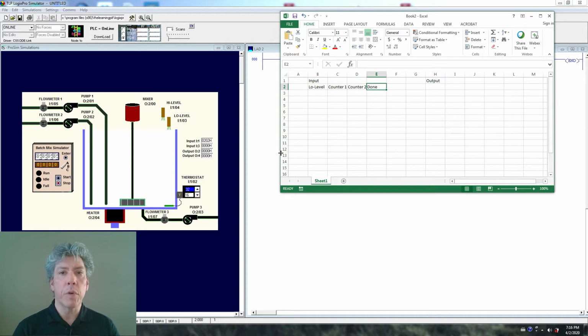And I'll want to pre-mix. So once I've got the chemicals in the tank, I'll want to mix them for a certain amount of time. Now, a lot of times it's a bad idea to use a timer when you should use a sensor. In this case, I don't have any choice, right? I don't have a sensor to tell me when the two components are completely mixed. It may be difficult, depending on what they are, to even make such a sensor. But, on the other hand, it may be possible. In this case, I don't have anything that will allow me to detect when the mixture is homogeneous. I'll just have to mix it for a certain amount of time.